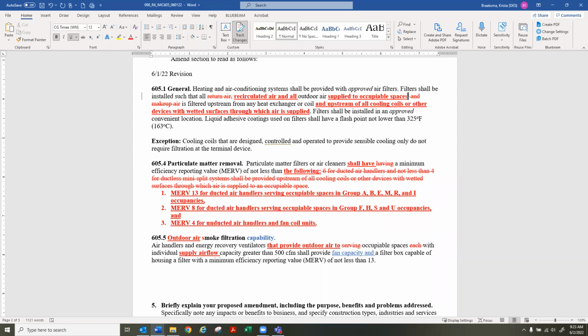So really 605.5 is only going to direct you to the group two MERV 8 filters. And then Eric, as you said, the air handlers and energy recovery is spelled out in 605.5, but not above. But I think you're giving a long enough laundry list up there of equipment that tells you you need a filter for anything coming into the space from outside. I don't know if you actually need 605.5 if really you're only pointing at F, H, S, and U. Those were just my takes on reading that.